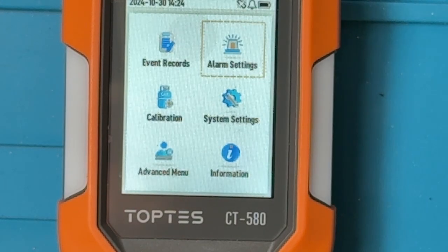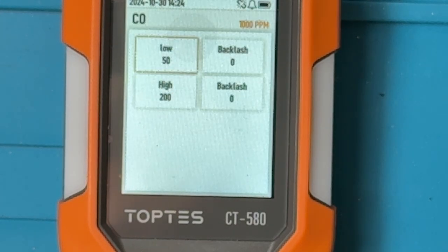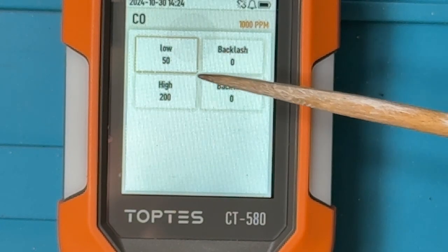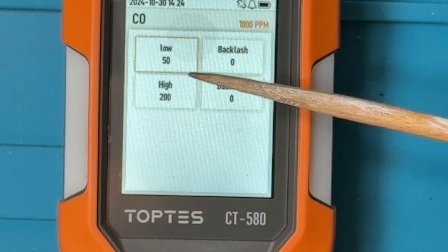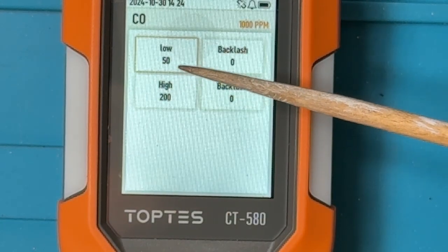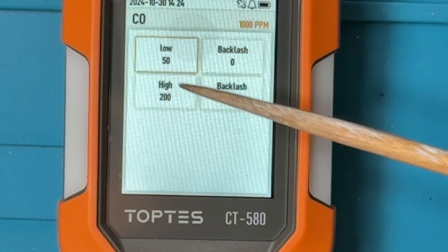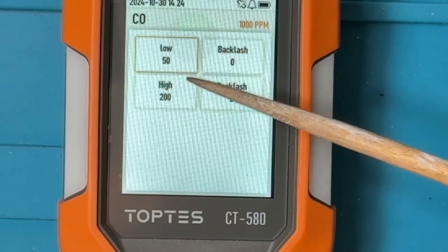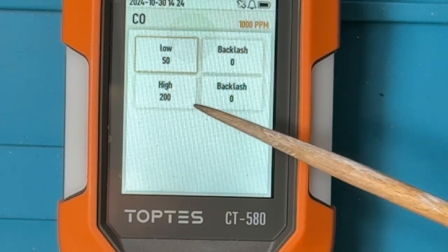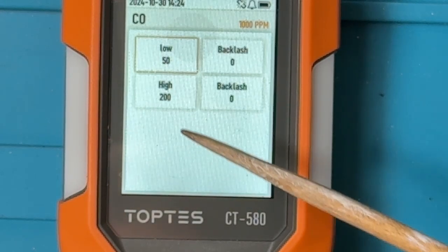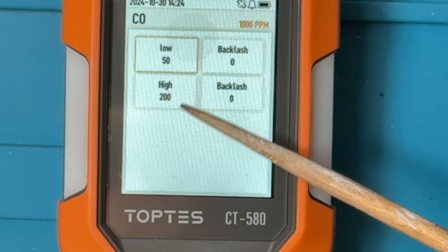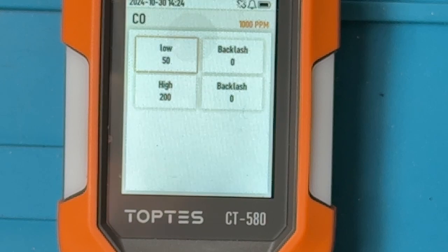We have alarm settings here, and if we look into this page, we see that we can set a few different thresholds. So we can set the threshold for what constitutes a low value, in this case it's set to 50. That's the factory value. And what constitutes a high value of carbon monoxide, here it's set to 200.